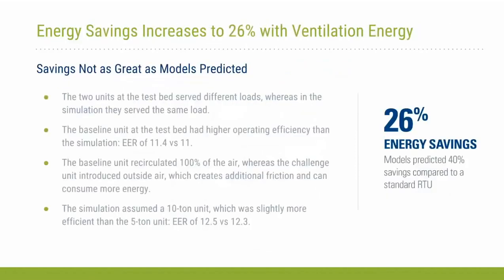Before we actually did the field tests, we also did a lot of simulation analysis to estimate what the potential savings would be across the nation. Comparing the results from simulations to actual field performance is always a bit tricky, because simulation models are always ideal and don't reflect the true field conditions. However, the simulations serve a purpose, to provide some qualitative comparisons between two alternate designs. And some of the differences that you find between simulation and field tests are because the two units that we tested serve different loads, whereas in simulation they serve the same load. And then there were also differences in EER of the standard unit. In the field, it was 11.4, which was slightly higher than what was used in simulation.